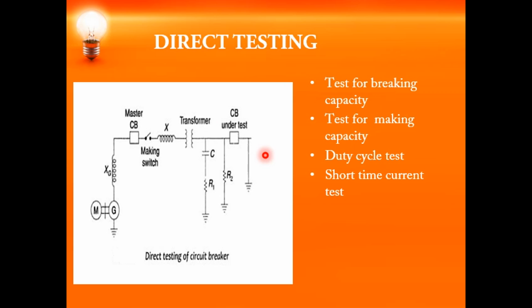If you have a circuit breaker in a power system, how will it work? It will be subjected to a high restriking voltage, is it not? The same large restriking voltage is made to appear across the circuit breaker under test. You can see the reactor X. This reactor is to control the short circuit current, as I've already told you. You have the capacitor C, R1 and R2. They are used to adjust the transient restriking voltage which you are applying across the circuit breaker.